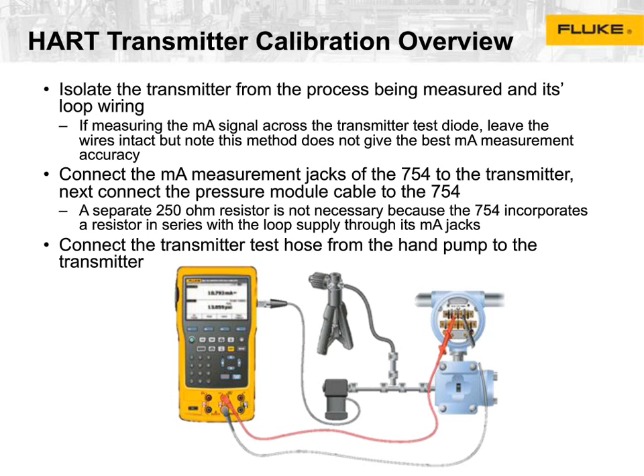So the first thing you have to do is isolate the transmitter and the wiring. If you're going across the test diode, as it says, you have to leave the wires intact, but you don't get great milliamps accuracy there, so it's probably not the recommended method. You have to connect the measurement jacks as shown in the diagram and connect the pressure module cables. Again, like we saw in the previous slide, connecting the pressure module directly to the pump will give you the best results. You don't need a 250 ohm resistor. The 754 has it built in. And then last but not least, you have to connect the test hoses.